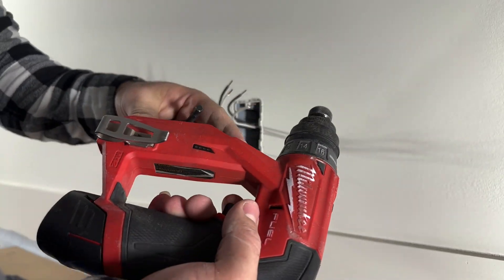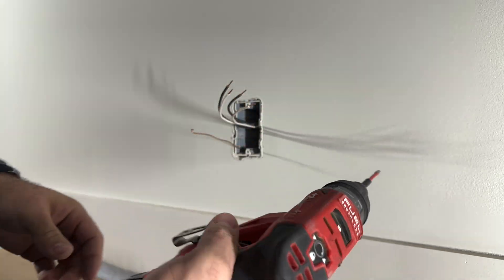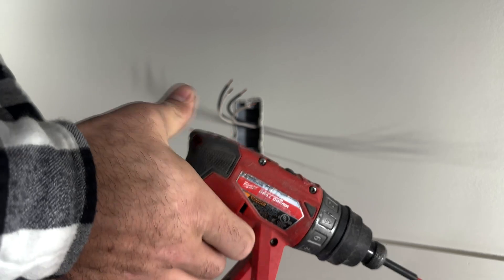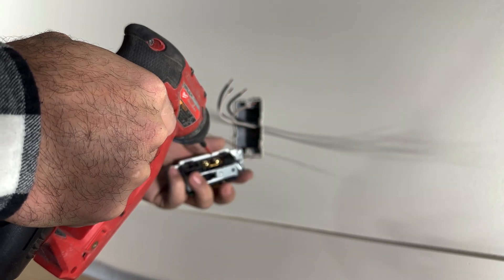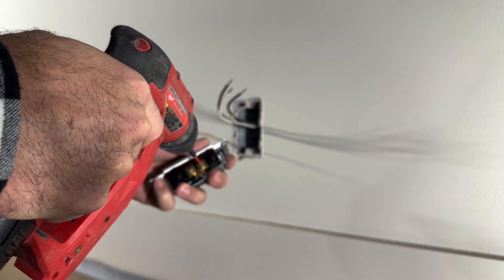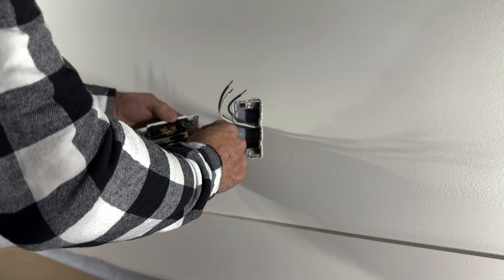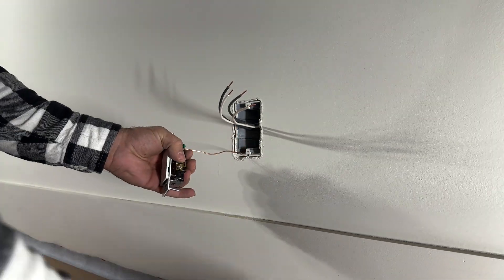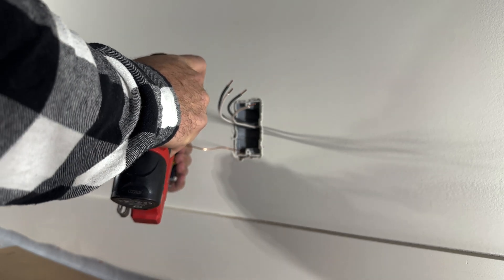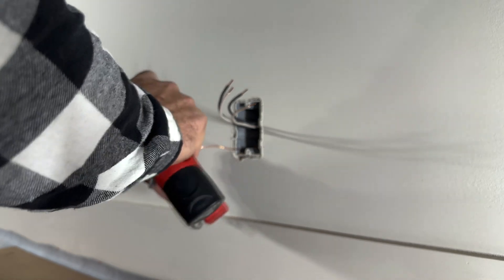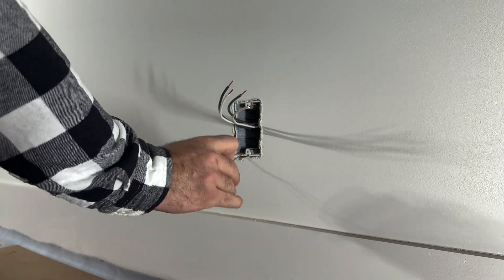We will swap out from a number two Robertson to a number one Robertson in our drill. Make sure our screws are loose. And we will start with the ground wire. It is very convenient when you place your ground wire on the left side of the box because that is where the ground screw for the receptacle is located.